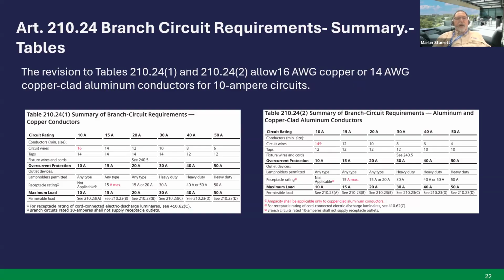Next slide. Article 210.24, branch circuit requirements summary tables. The revision to Tables 210.24(1) and (2) will now allow 16 gauge copper or 14 gauge copper-clad aluminum conductors for 10 amp branch circuits. So this is the introduction of 16 gauge copper wire that can be used for a 10 amp circuit. As we go on with this series, we'll notice this change in Article 310 and a lot of the cable articles. So now the minimum size will be 16 gauge copper. Next slide.